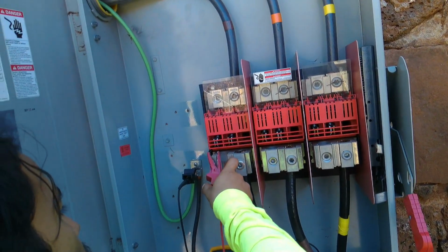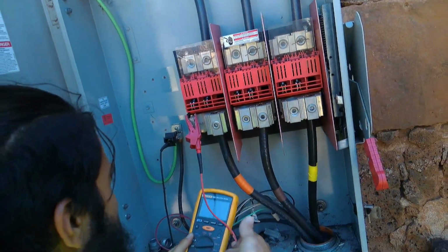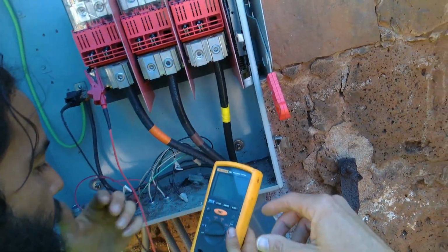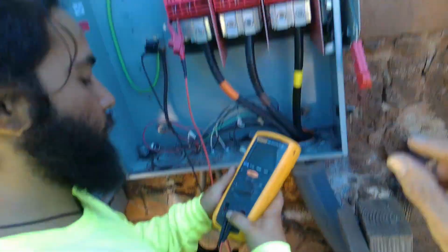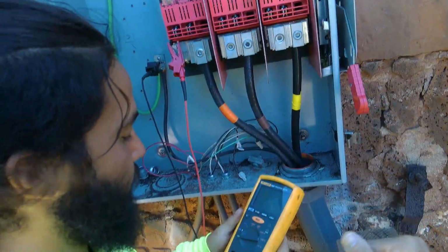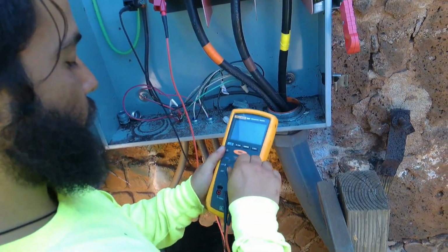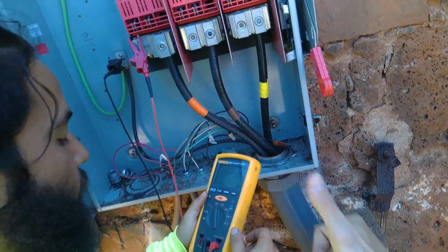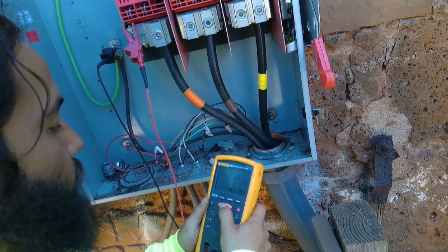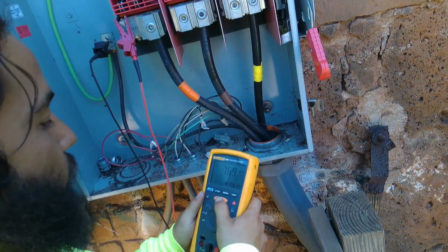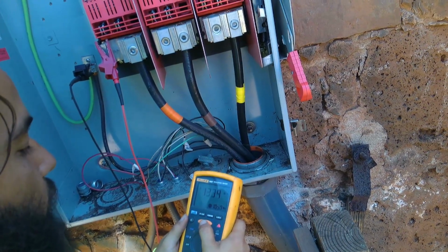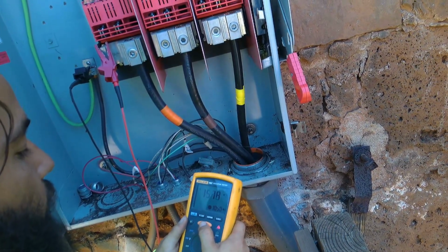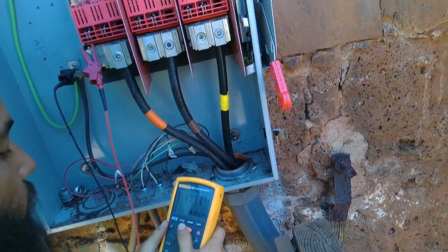So this motor runs, bring it out a little bit. Yep, this motor runs at 480 volts, so we can safely charge it up for a short period of time with 1000 volts DC. So we're going to put it on 1000 volts and then we're going to hold down the test button. That's a good reading. You can release the test button.